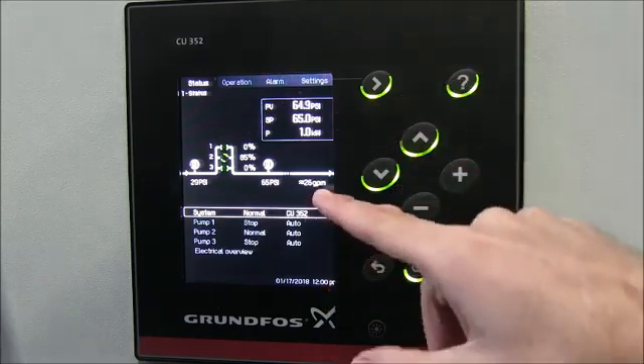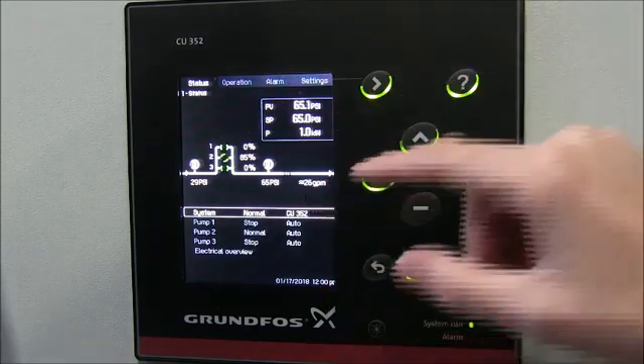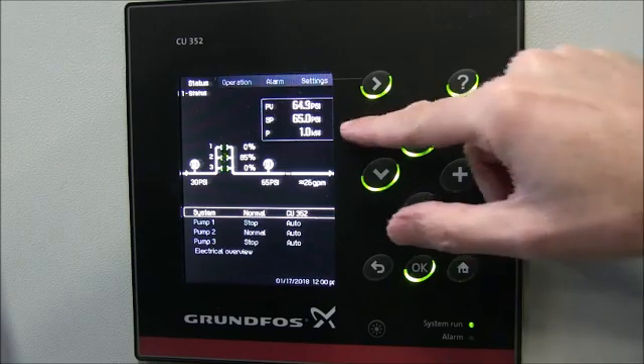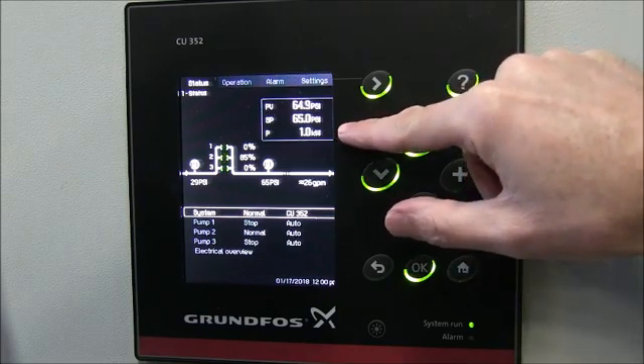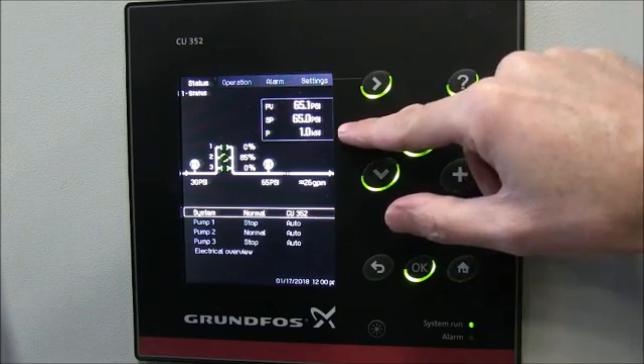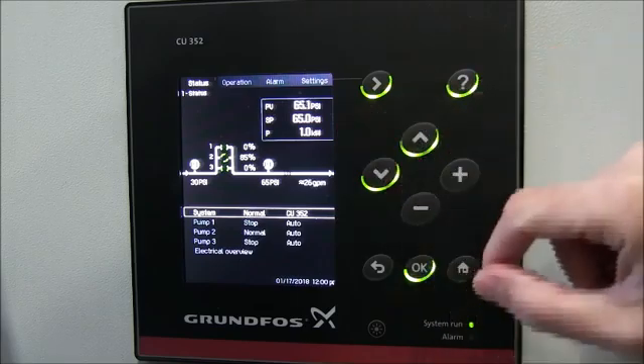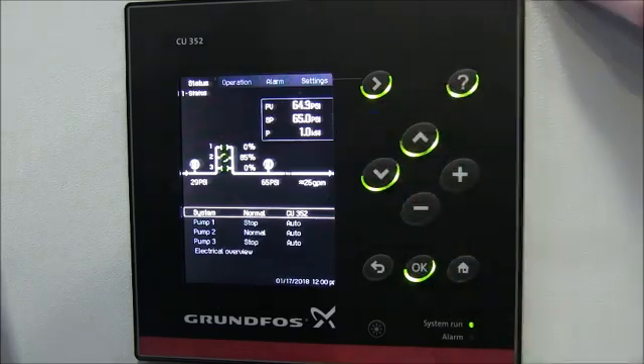We've got an approximate flow rate of 26 GPM and our power is one kilowatt. Power is the notable item on the screen here because right now with one pump running at low flow we're using one kilowatt of energy.